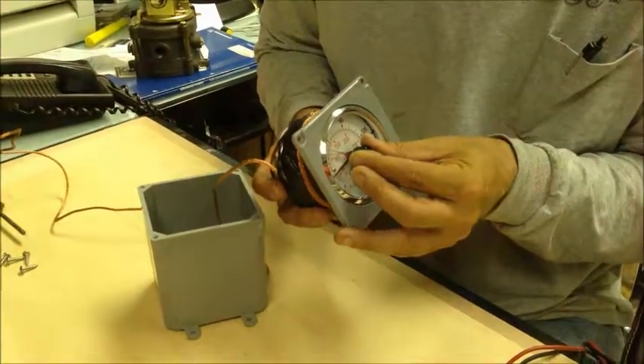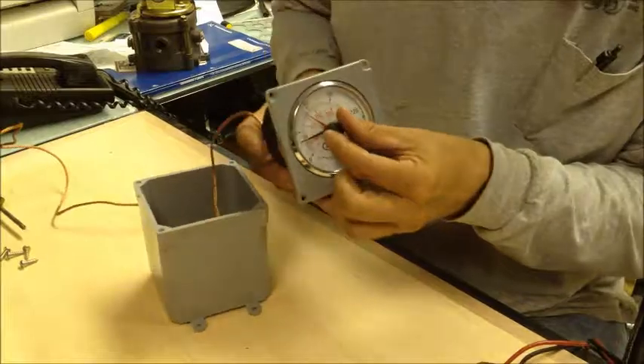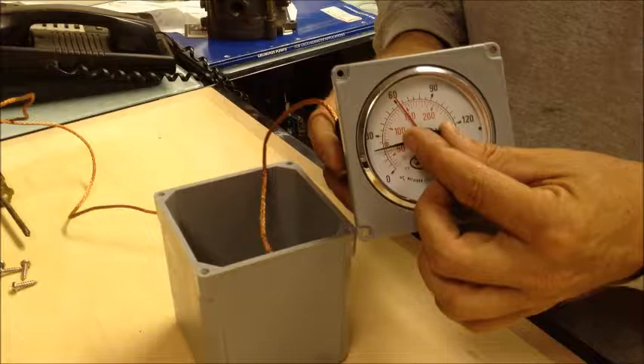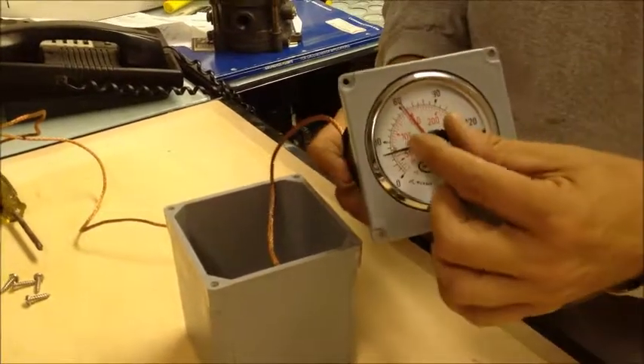So usually we wire these temperature switches normally open and we set the action level, you know, somewhere around, if it's like an SV system, we usually put them around 140 degrees because we don't want them to melt the PVC.